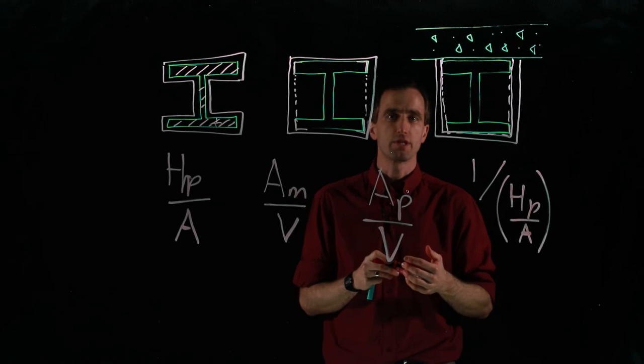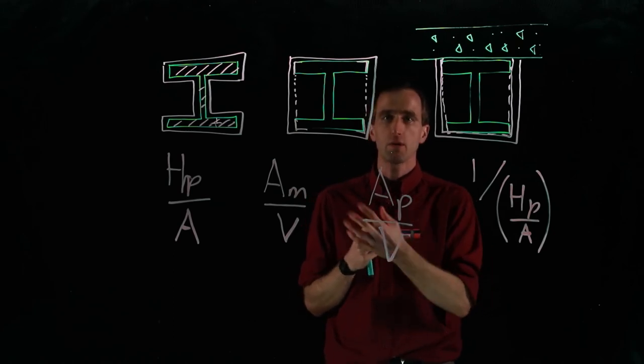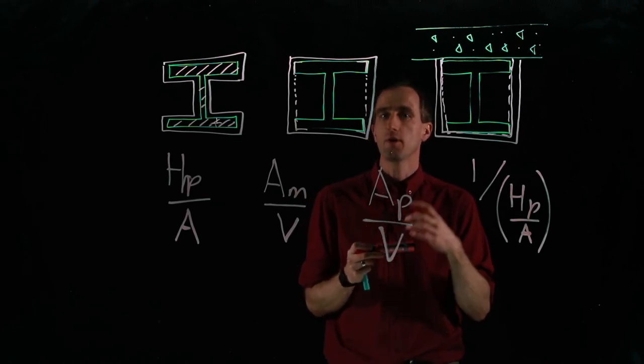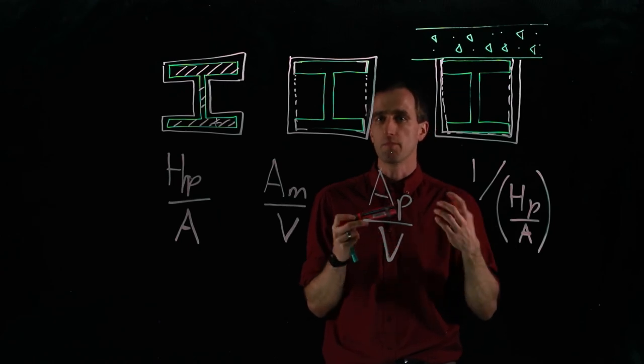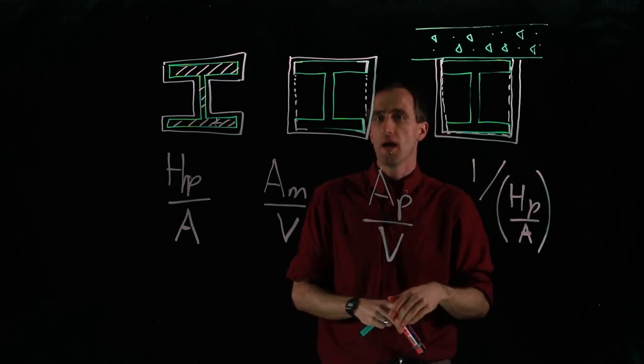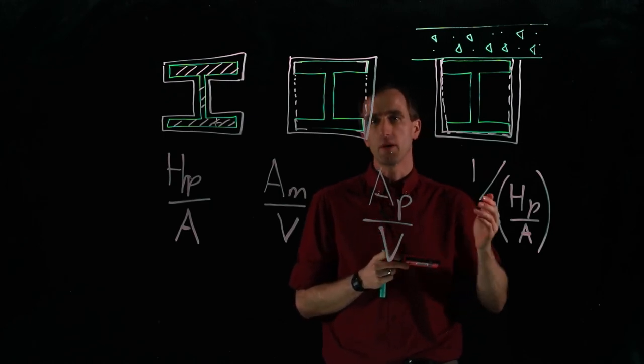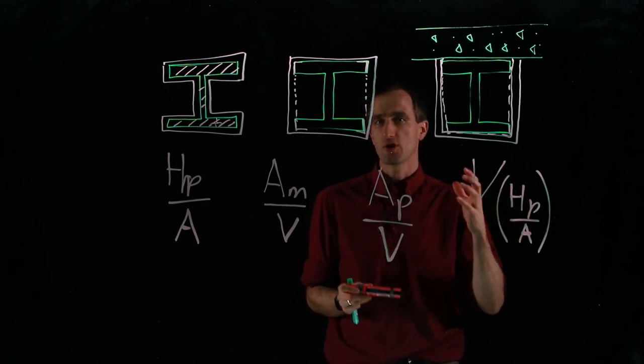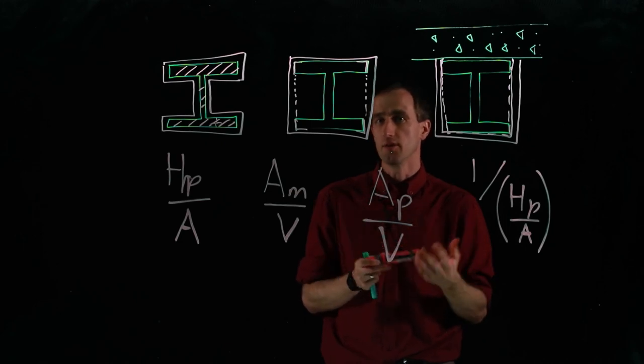As I mentioned, use this to try to get an understanding and use this to try to optimize your passive protection cost. You'll quickly see when you start playing with these calcs - if you have a very slender member, especially purlins and long sections with thin webs, they heat up so fast you sometimes cannot even protect them at one hour or two hours.